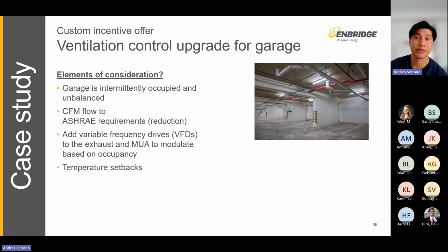Same thing, what are some of the elements of consideration? First, as we know, the garage is intermittently occupied and unbalanced. We do know that the garage is not always occupied, so we can definitely see some savings there, especially if it's running 24/7. Another thing to consider is the amount of fresh air that is being pumped into the garage space. Is it too much fresh air? Are there ways to reduce that amount of fresh air while maintaining ASHRAE requirements? The next thing to consider is, can we add variable frequency drives to the exhaust and makeup air to modulate based on the occupancy? We can also look at temperature setbacks. What is the temperature that the air is being heated at, and are there ways to decrease that temperature?